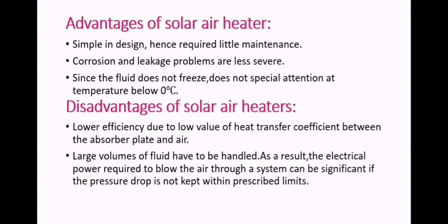Next, the disadvantages of solar air heaters are: the value of the heat transfer coefficient between the absorber plate and the air is low, and this results in a lower efficiency. For this reason, the surfaces are sometimes roughened or longitudinal fins are provided in the airflow passage. Next, large volumes of fluid have to be handled. As a result, the electrical power required to blow the air through a system can be significant if the pressure drop is not kept within the prescribed limits.